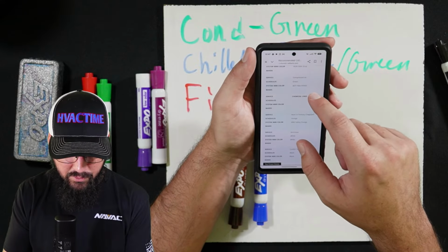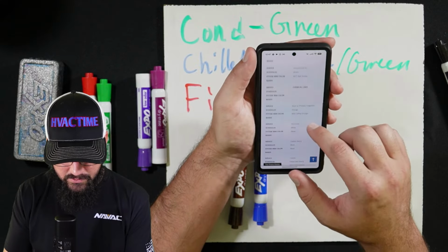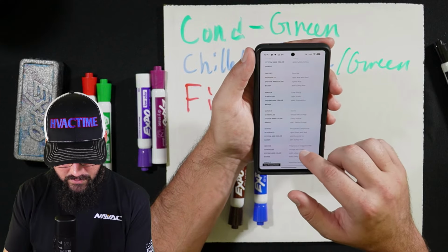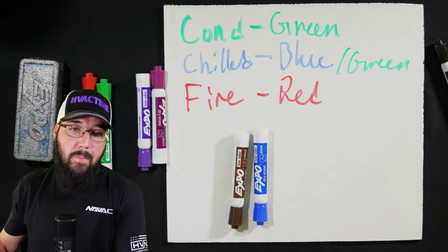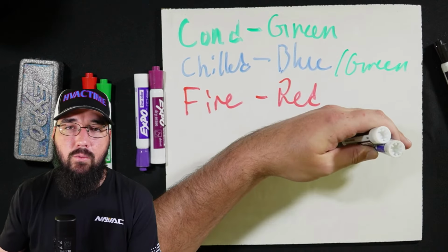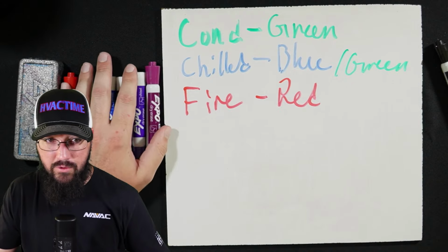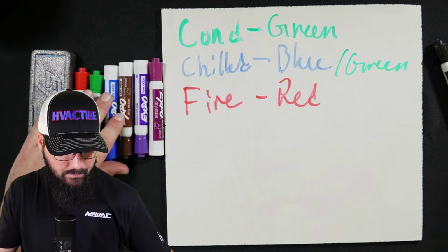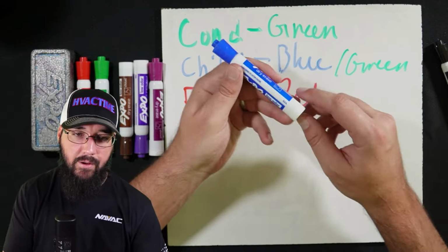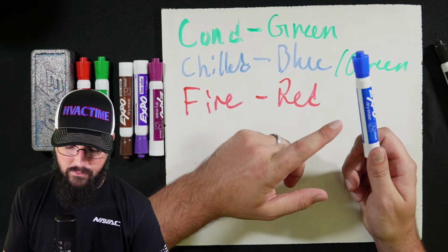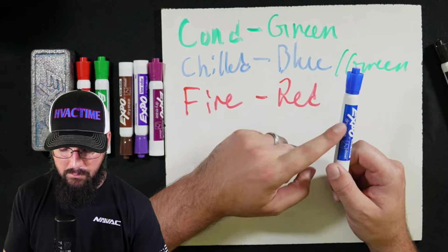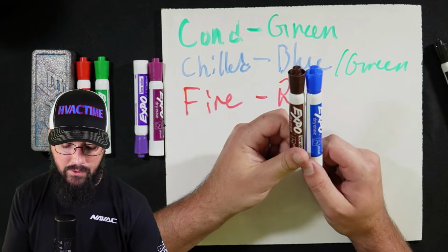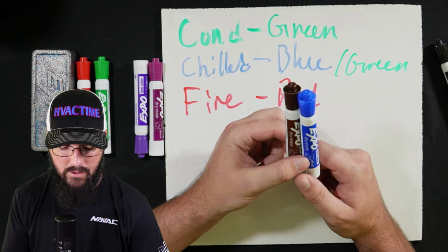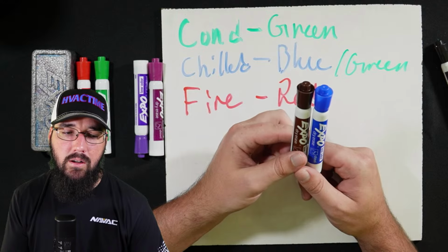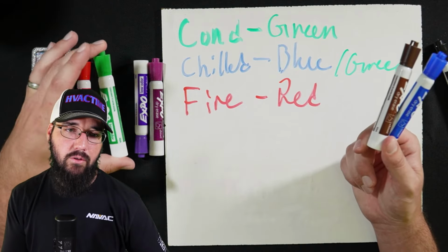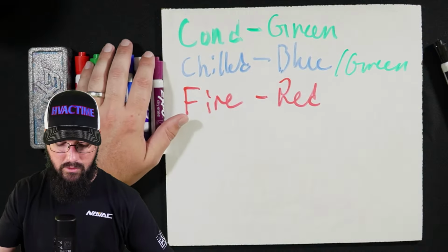Compressed air. So this one shows compressed air is green, but that's not what I'm used to seeing. I don't usually see that as green. Anyway, I think part of the point there is it does fluctuate depending on where you're at, what plant you're in. But in terms of your general question, it's very common that blue will be used for compressed air. I've seen blue and I feel like brown. I've seen both blue and brown used for potable water. And then yeah, your non-potable is typically going to be green, or like I said, chill water. It'll be sometimes blue.